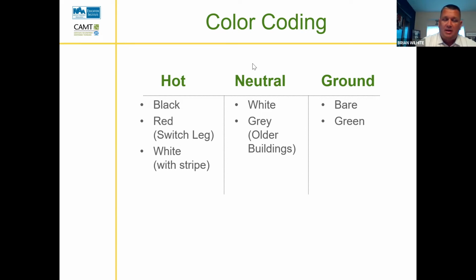But normally, hot wires are represented with black wire. Red is usually a switch leg. You don't see much of a black with a white stripe or red with a white stripe much anymore. Neutrals are white, gray in older buildings, and then ground, bare, or green. Note that these color codes are only for primary electricity. Primary electricity being 120 volts or 220 volts.